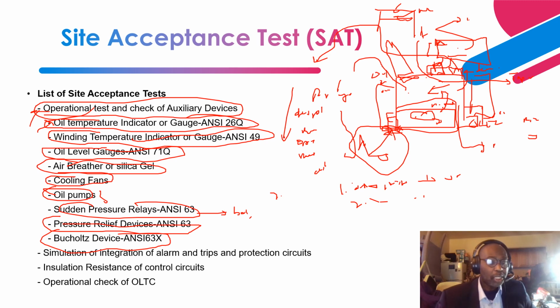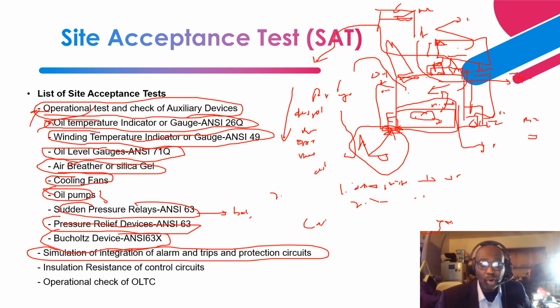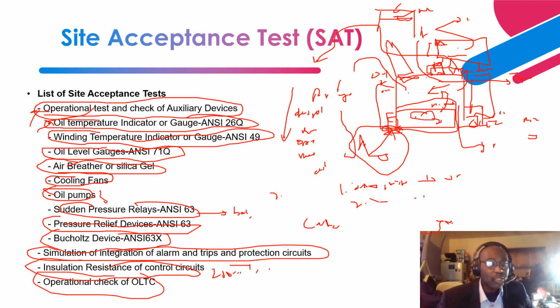Okay. So then the simulation of the integration of all these devices and the alarm circuits to either a SCADA system or a central control room, a centralized operational center. The whole part of that alarm and trips will be checked. Next is the performance of insulation resistance of the control circuit, right. 250 volts DC or 500 volts DC is utilized to test these control circuits to make sure there's no damage to the insulation of these control circuits. Next is a check of the OLTC.